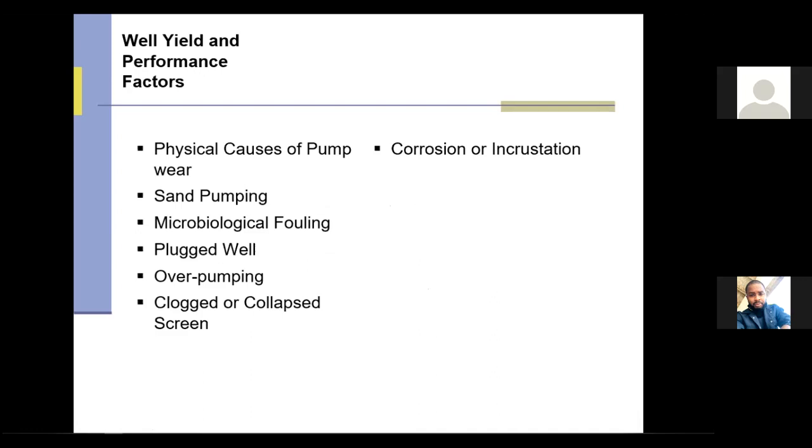And sometimes you have to do something called shocking the well, which is adding disinfectant, usually in the form of chlorine, to the bottom of a well to dissipate the iron bacteria. It could be plugged. It could be plugged by some clays, or something happens below. The metal of the screen can get plugged because of incrustation.